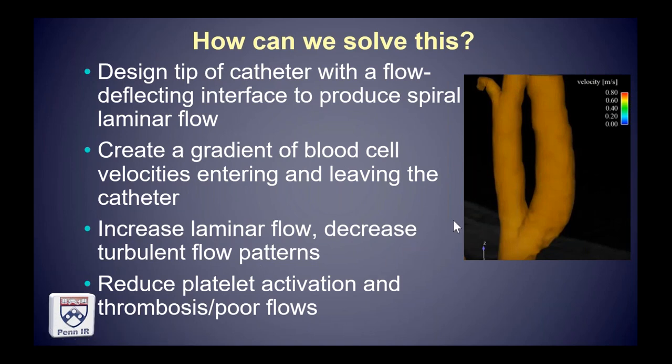How do you solve this problem? This has been a perennial problem since hemodialysis catheters have been around. As so often is the case in biodesign, you look at what the human body has already done through billions of years of evolution. If you can create a phenomenon of spiral laminar flow, which decreases near-wall shear stress and creates a more organized, less stressful environment for blood flow rheology, that becomes a protective effect.